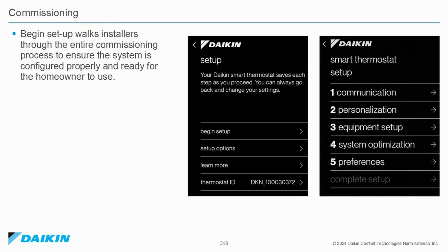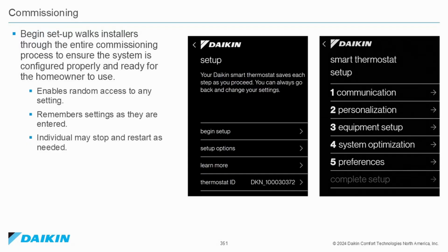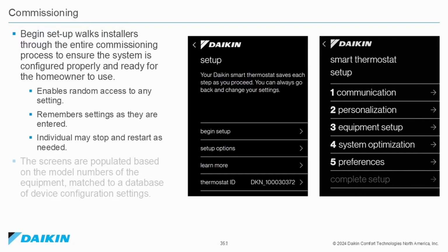Begin Setup walks the installers through the entire commissioning process to ensure the system is configured properly and ready for the homeowner to use. It enables access to any settings and remembers settings as they are entered. The installer may stop and restart as needed. The screens are populated based on the model numbers of the equipment, matched to a database of device configuration settings.